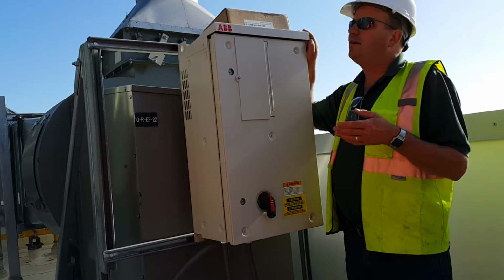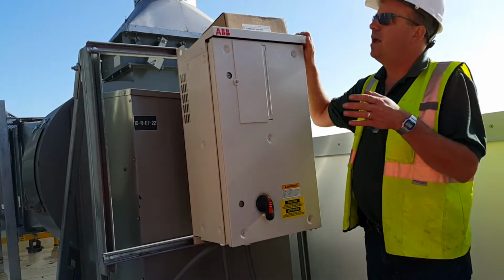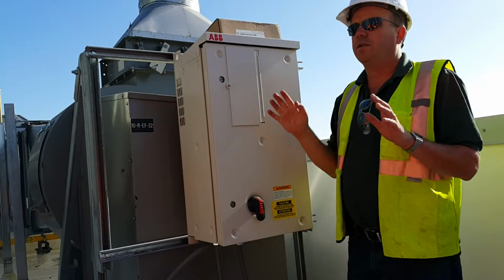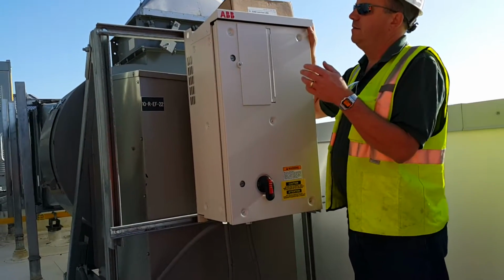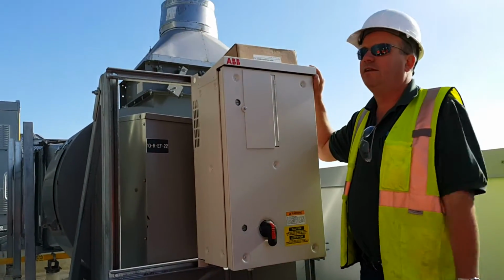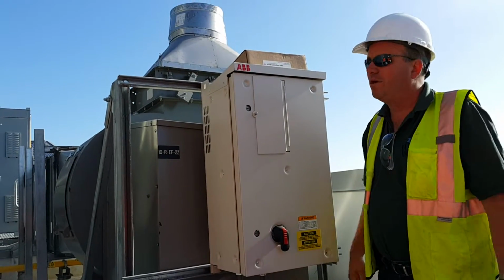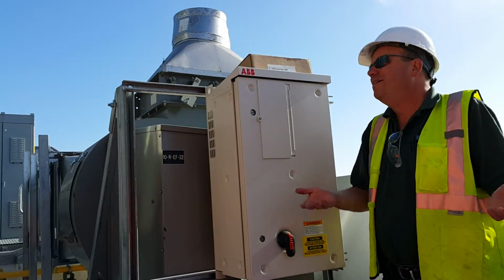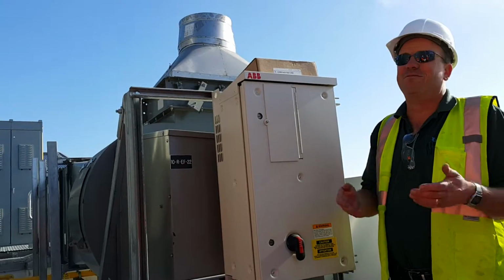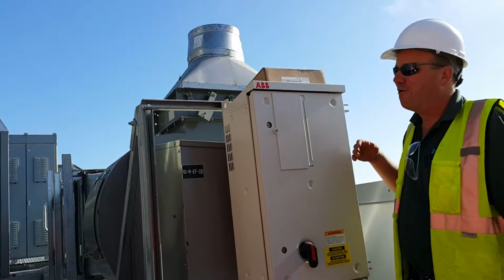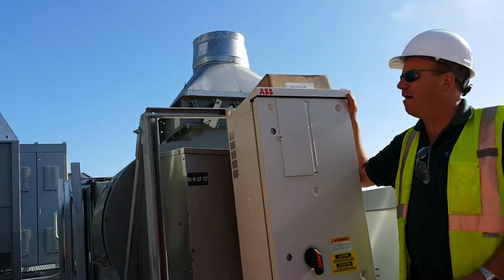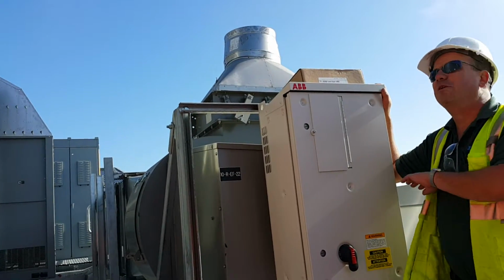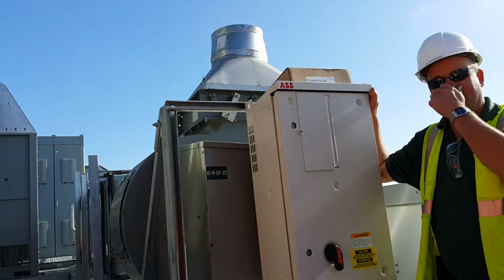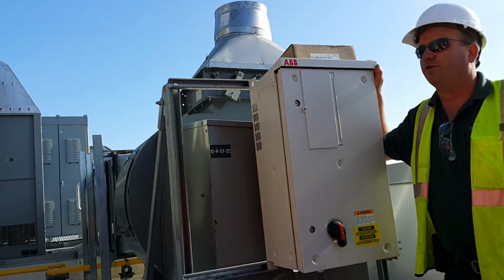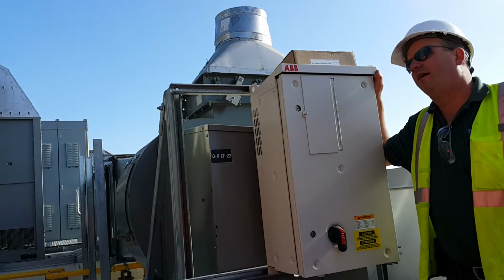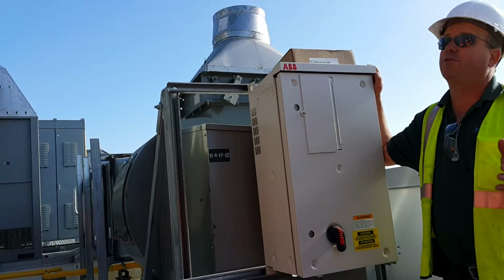A lot of times, guys are troubleshooting and they've got a problem. They don't know what the problem is, and they look and it's got under voltage faults in it. You know, the voltage going away. Well, at some point in its life, power's going to go out. It'll be generator testing or a storm or someone just turns the power off. Under voltage faults in memory, don't even worry about it. So they start chasing up the wrong tree.